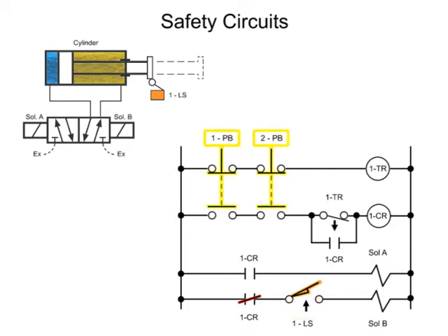When both push buttons are in the unactuated position, the timing relay is energized and the normally open-timed open-timer contact is shut. No power can flow to the control relay. If an operator depresses a single push button, power to the timing relay is removed and the off-delay timer starts to time. Only when an operator depresses both buttons within the off-delay timer countdown period can power flow to the 1-CR control relay and energize the bypass circuit.